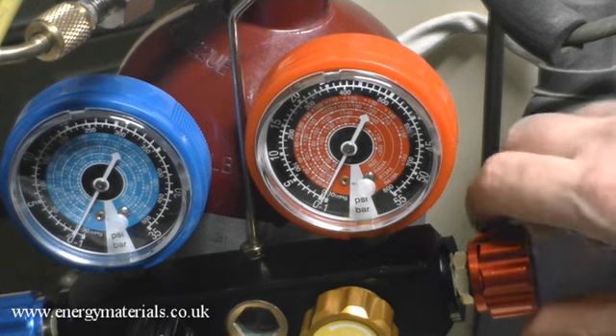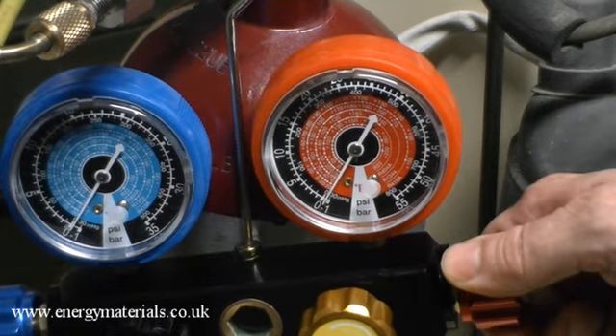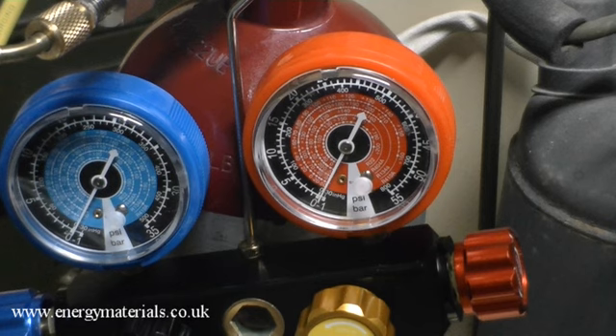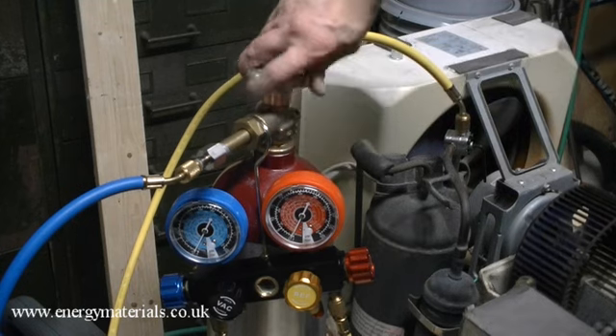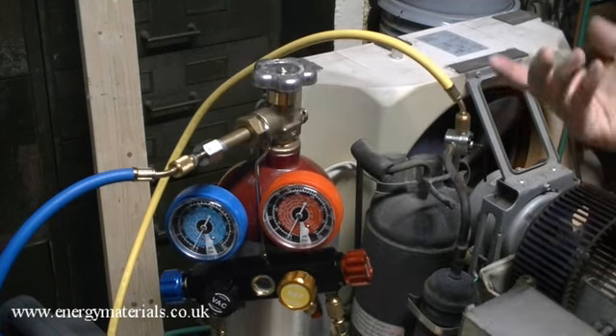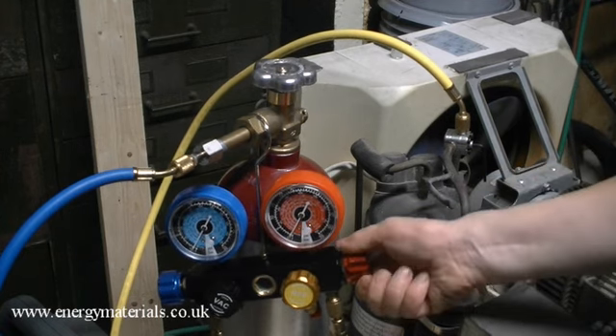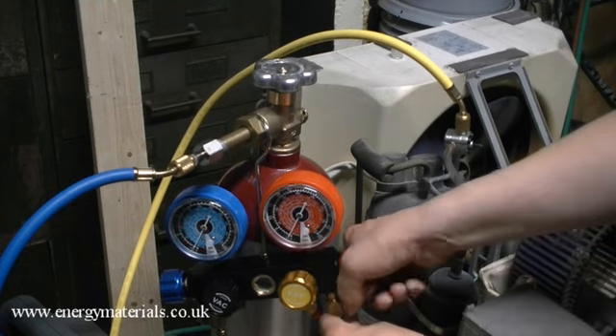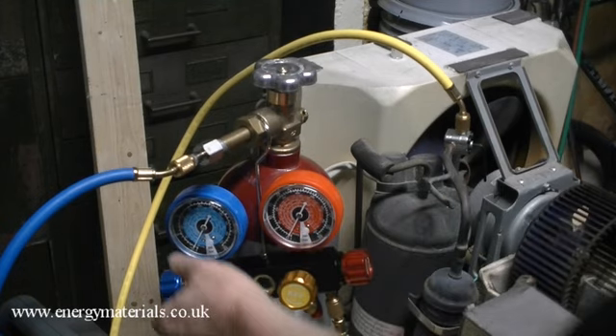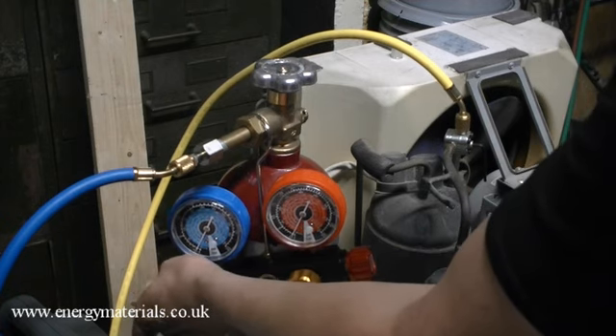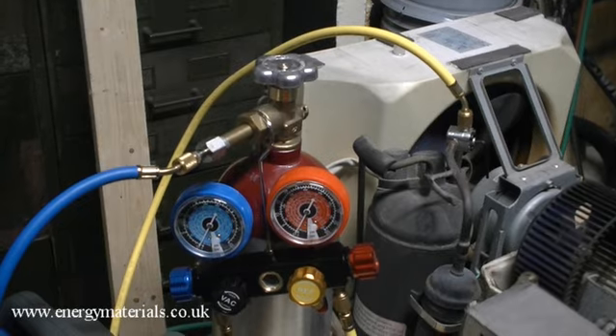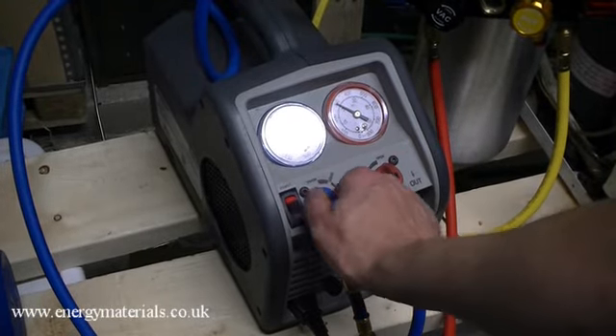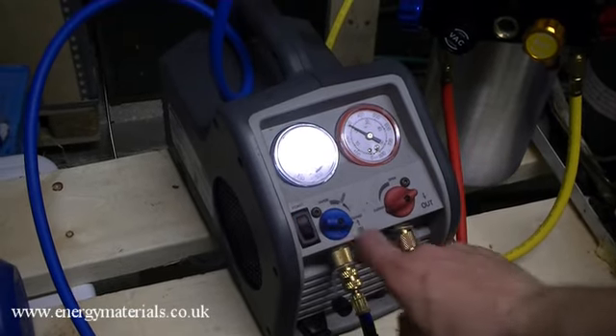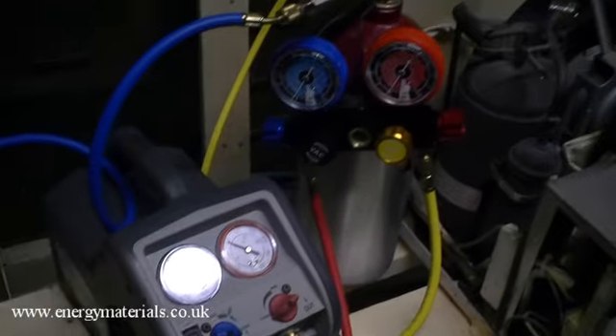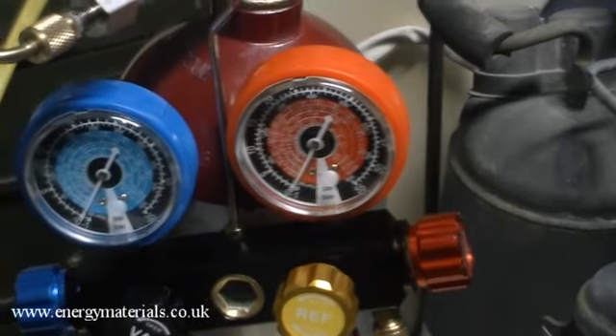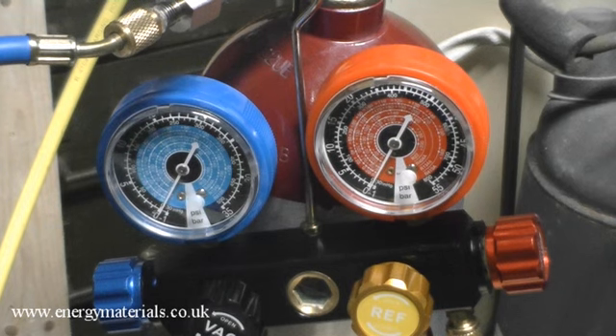Okay, let's close our inlet. And the pressure is not rising. So I'm going to close the tank. I'm going to close the inlet. The inlet's already closed. To see if this pressure rises in the morning, if there's anything worth in addition to recover. We'll close the outlet, go into our recovery machine. I'll turn the recovery machine off. So I'll turn that closed, and off. Silence. And that's it. We'll see what our inlet gauge is in the morning. If we got anything, then we'll continue the recovery. If not, then we'll go to the next step and split the unit.